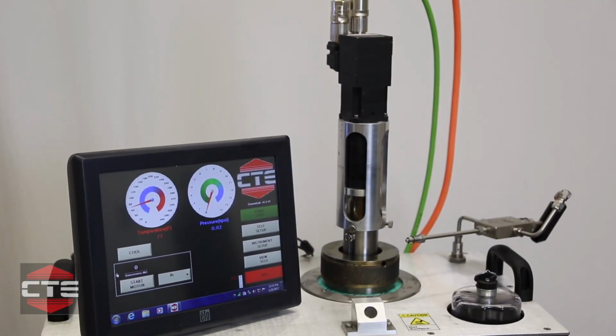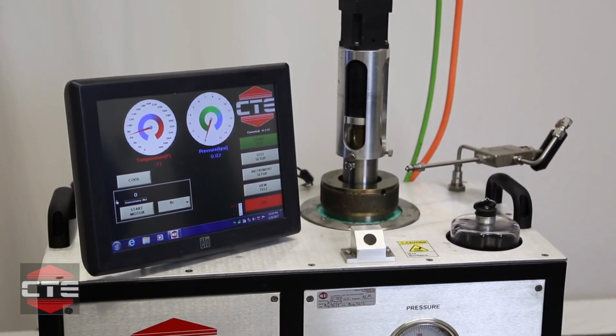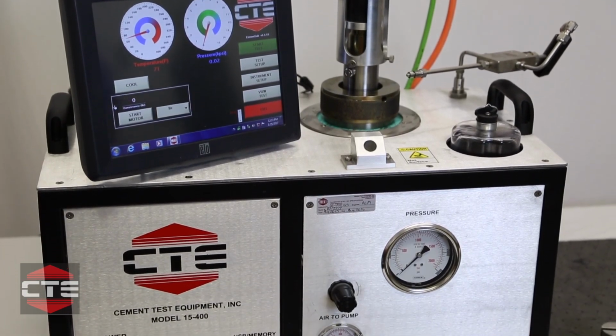As I mentioned earlier in the gel strength calibration, if you're having problems getting your raw value to settle on one value, then you can reinstall the Mint system files on here. For those of you on the consistency portion of this, I didn't mention this, but if you cannot get a good calibration, this would apply to you also. Mint system is the software that controls the motor. And these files over a period of time get corrupted. So you can reinstall those files through this procedure.